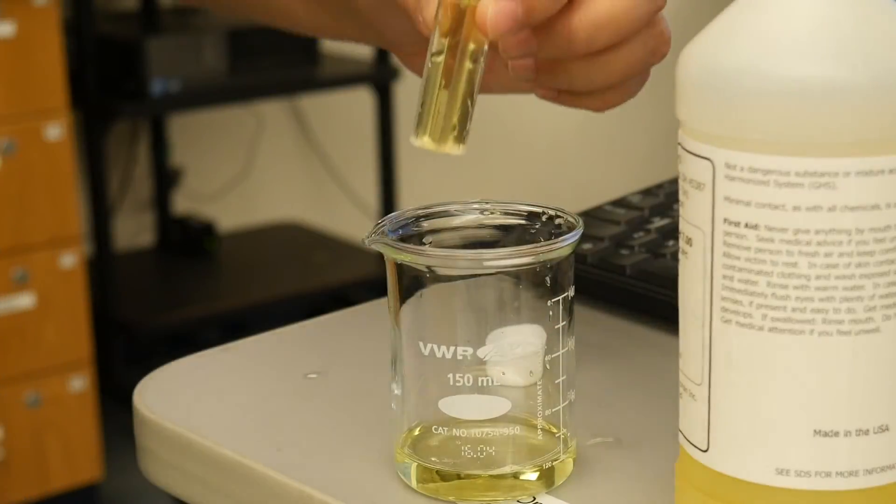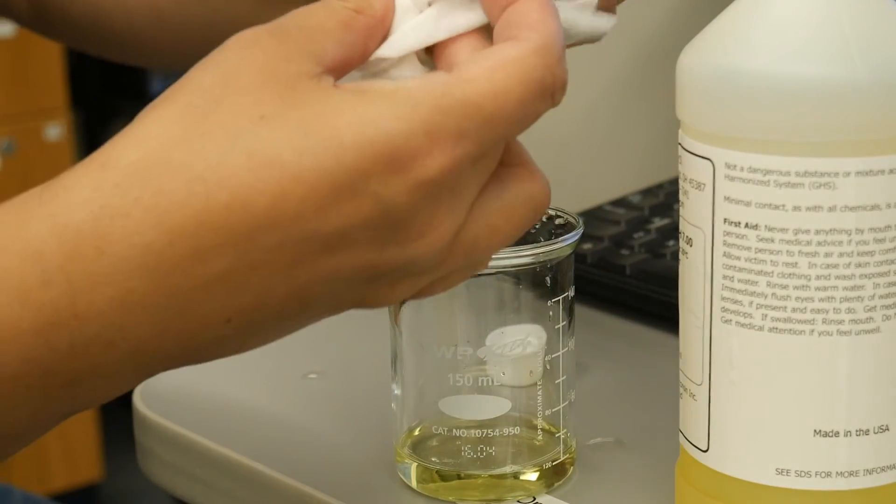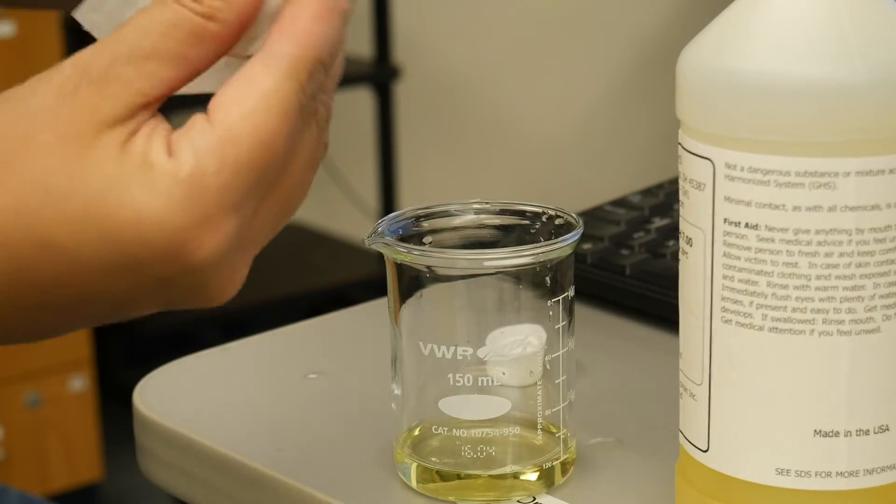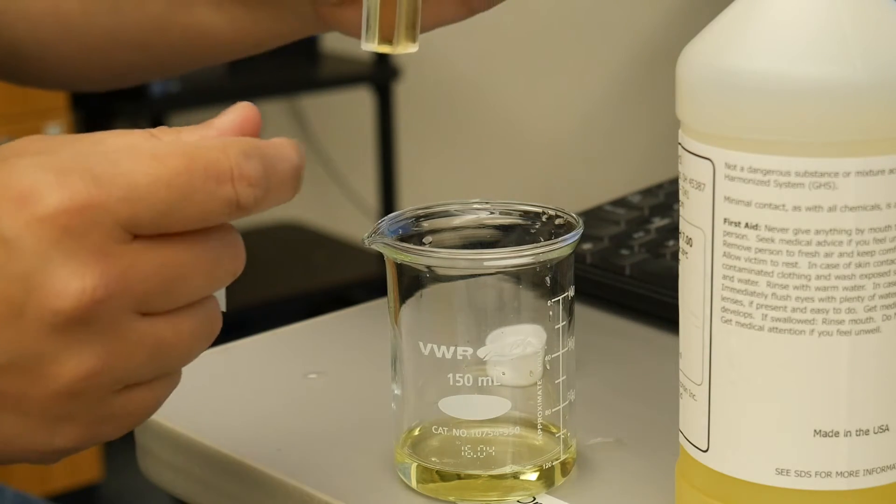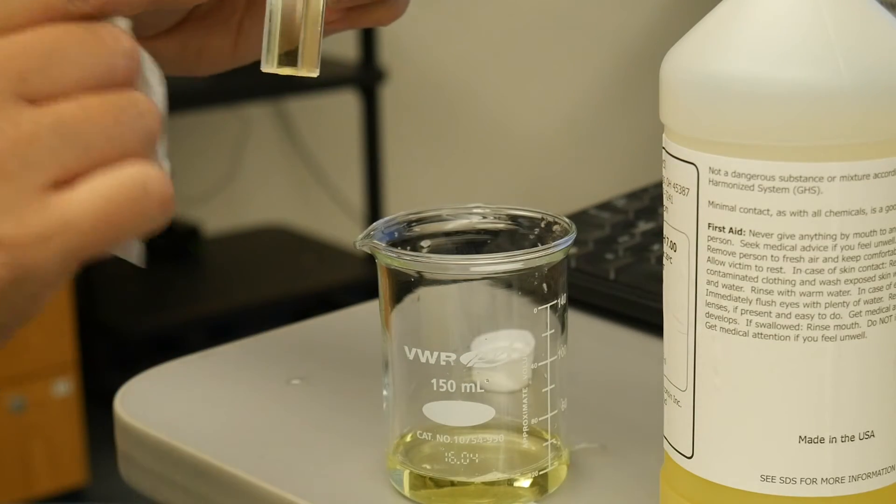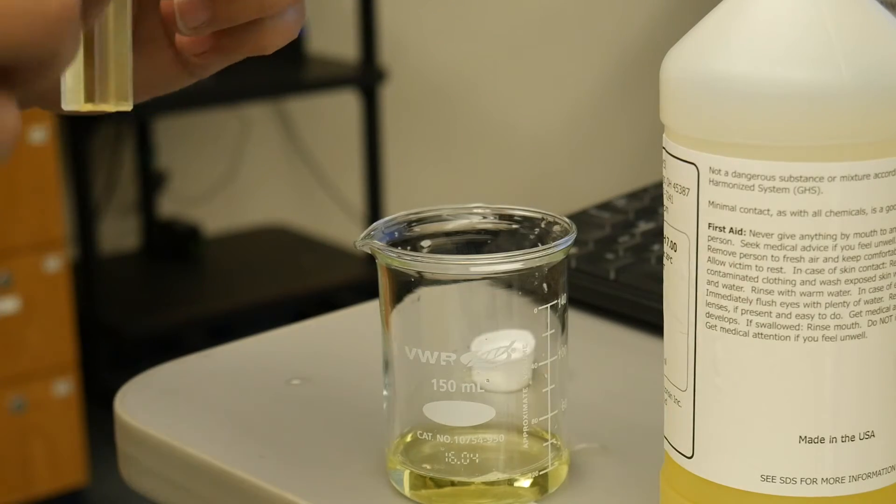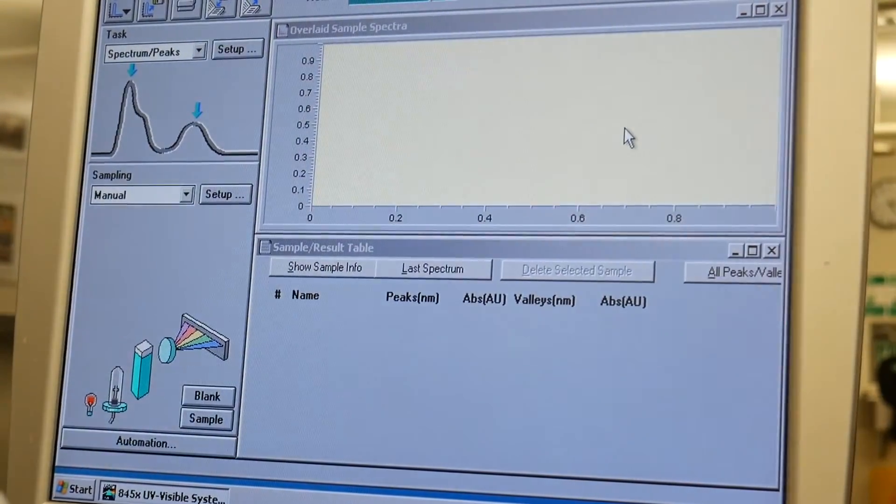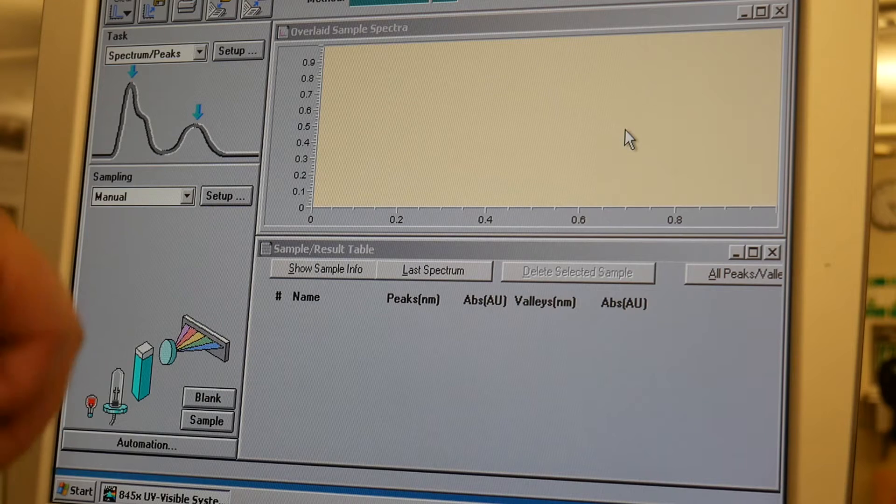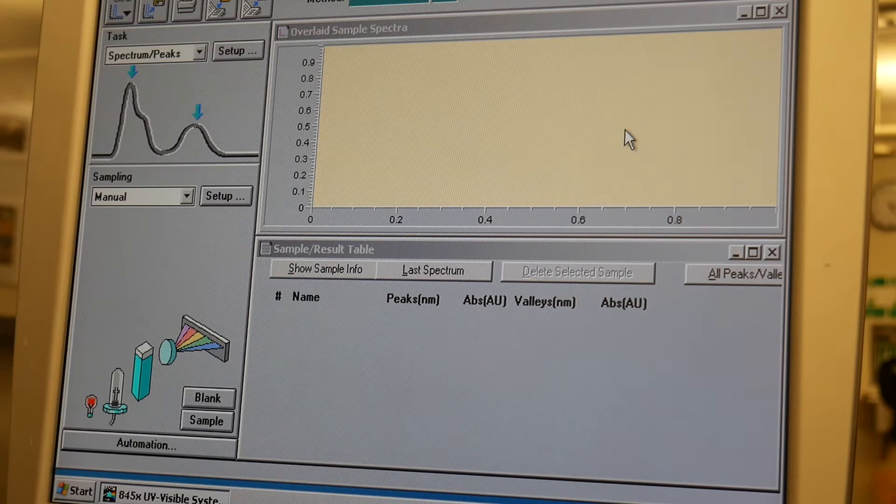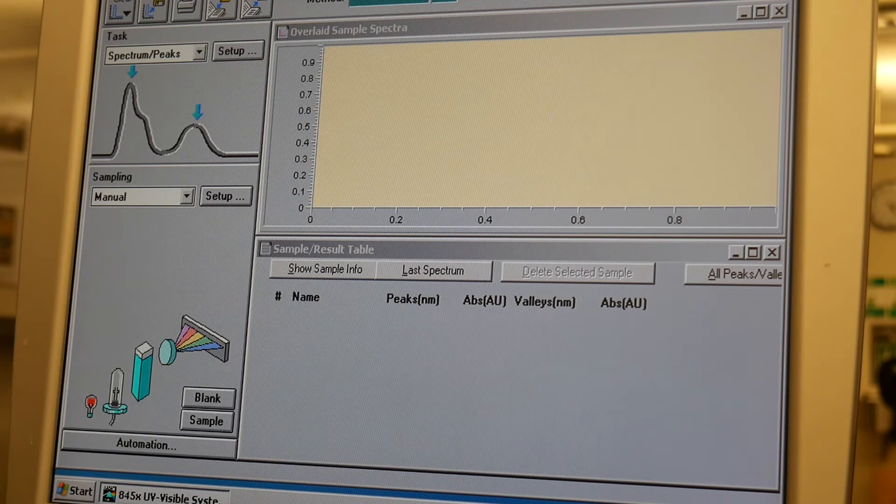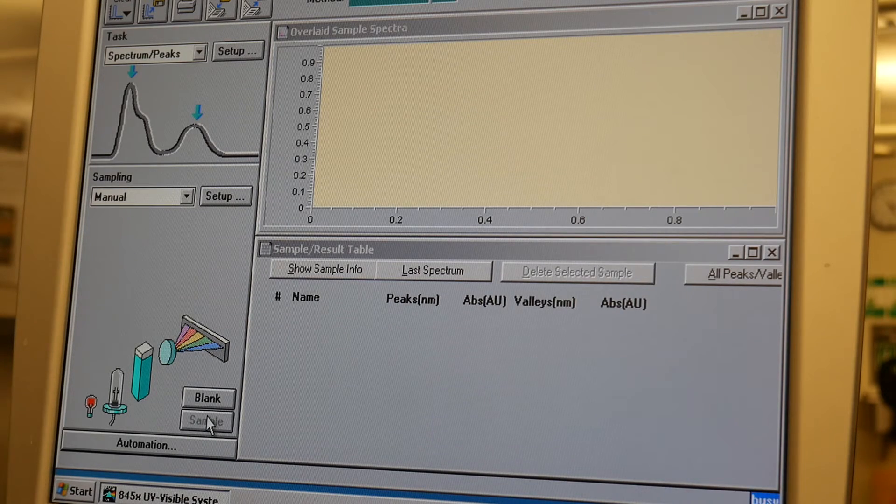Now, obviously, this is a messy business. You want to make sure you completely wipe down the cuvette before you install it in the cuvette holder. And again, you look for the little arrow to make sure you're putting it in the right way. Install it in the cuvette holder. And then now, again, I have a newer instrument here that I'm working with. So I could just press the sample button on the front. But if you're using one of the older instruments, you can just click the sample button right here.